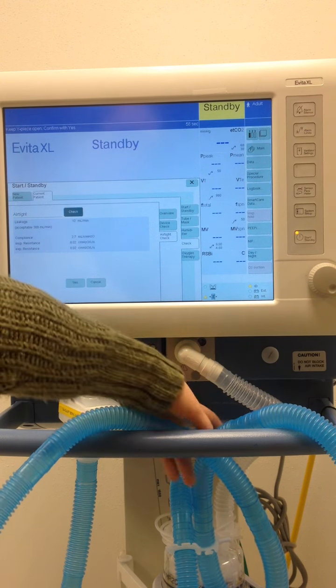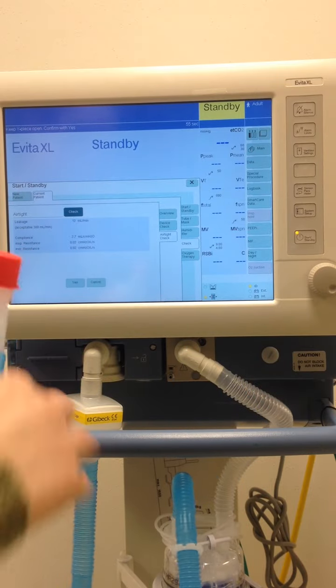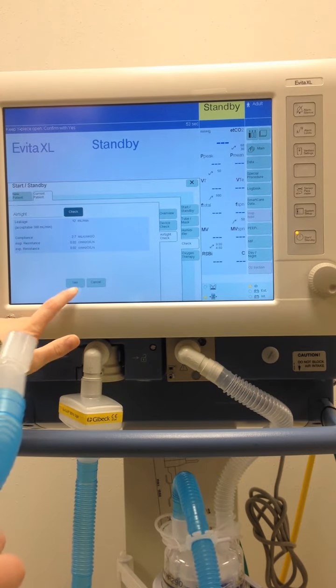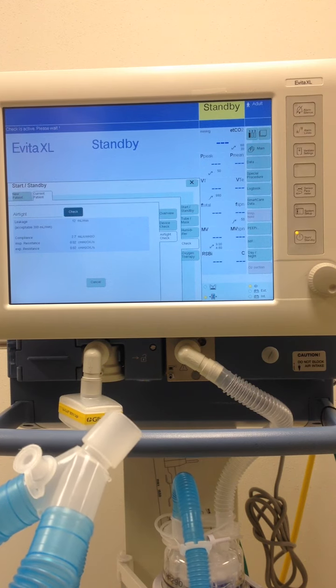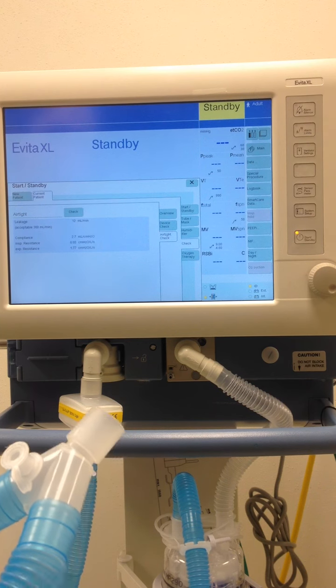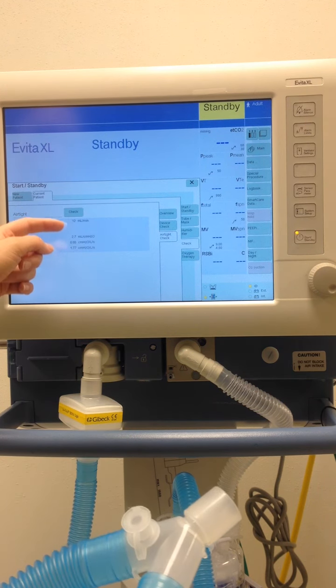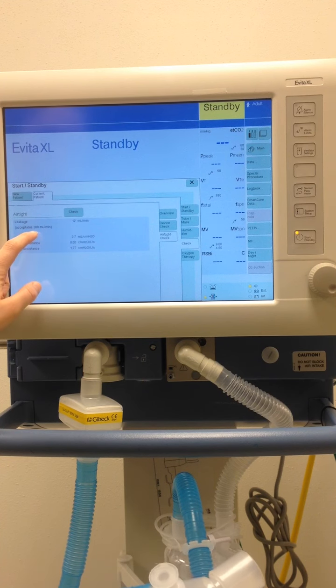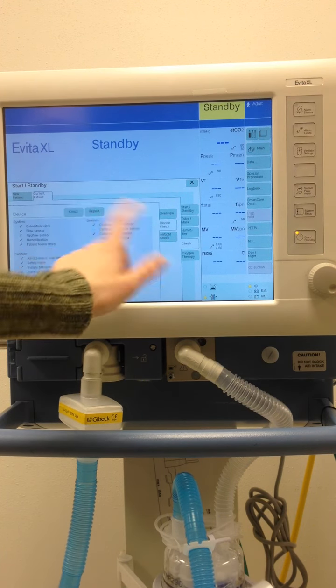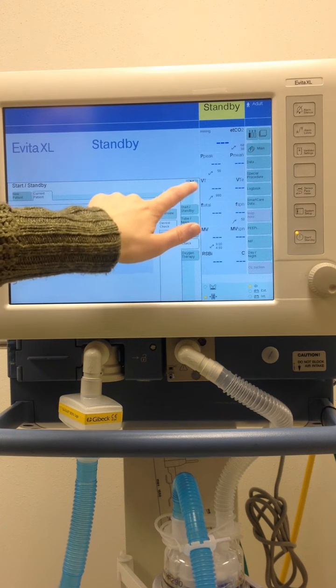And then keep your Y piece open and confirm. So we're just going to unblock our Y. Okay, and it shows you how much leak and compliance resistance. It tells you what the acceptable leak is, 300 mils per minute or less, and we're at 12. So we know that our check is good and our device check we passed, so we're all done with our checks. We can go ahead and set up for our patient.